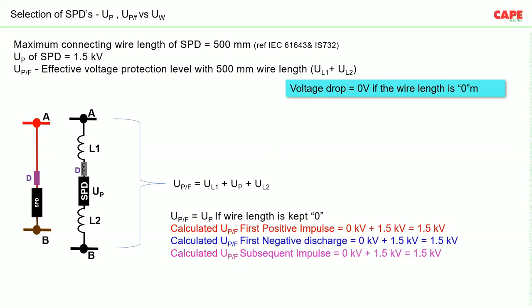The best case scenario is if we have a wire length of 0 meter. If we have a wire length of zero meter, the calculated UPF for first positive will be 1.5 kV, first negative will be 1.5 kV, first subsequent impulse will also be 1.5 kV. Because of this zero wire length, there won't be any voltage drop. And since the wire length is zero, di by dt becomes irrelevant. It is not that important. And it is again irrespective of lightning protection level.